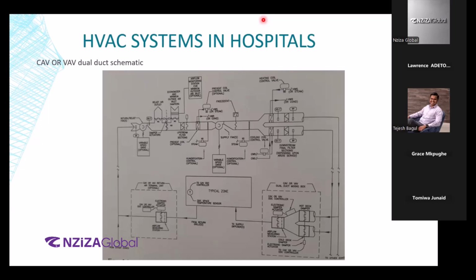So for calculating that, you start from the first point after the air handling unit, right? If you have a straight duct, that straight duct, as per industry standards, is calculated at 0.08 inches per 100 foot. So if it is 100 foot, the pressure drop will be 0.08 inch. Okay. Let's say you have 10 different accessories. Those accessories of that duct have a pressure drop associated with them. That is defined by another organization like ASHRAE called SMACNA. So it is given in the SMACNA guidelines how much pressure drop we consider for these particular accessories. Adding all of those pressure drops, going all the way up to the last point, is basically the calculation for your external pressure drop. Why external? Because it is external to the air handling unit.